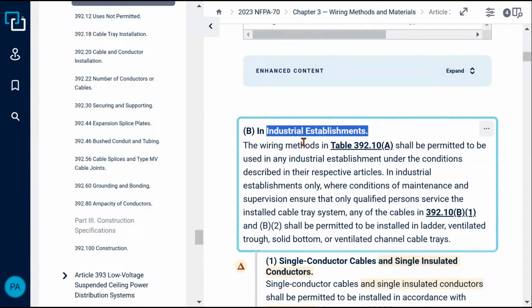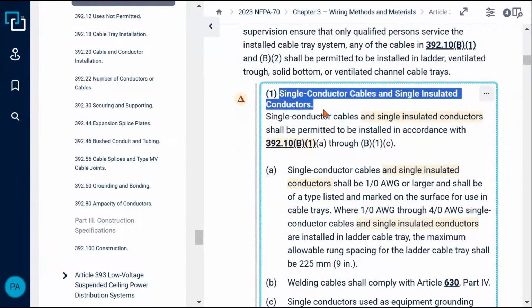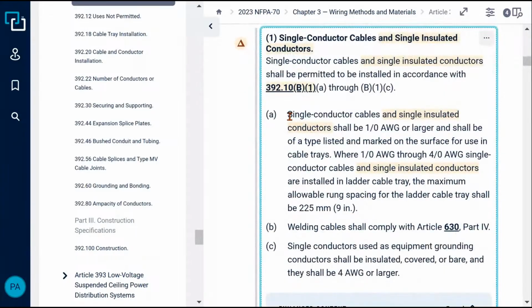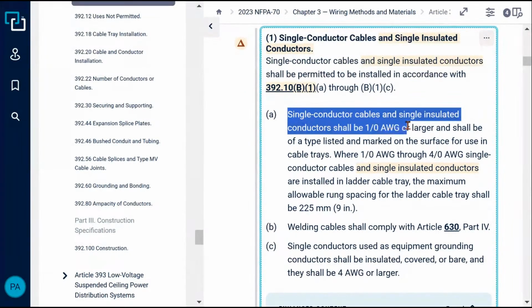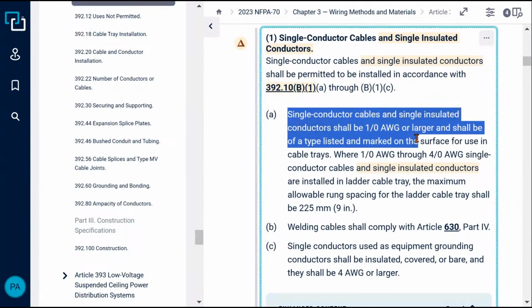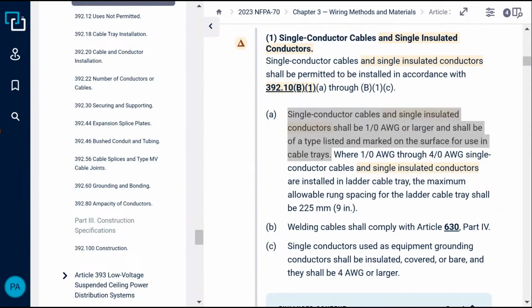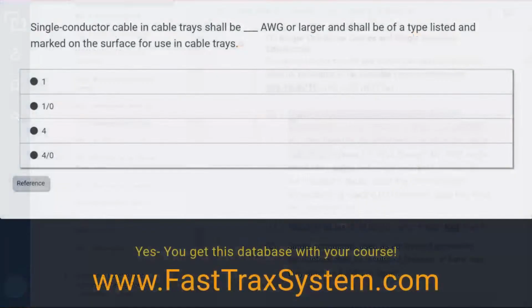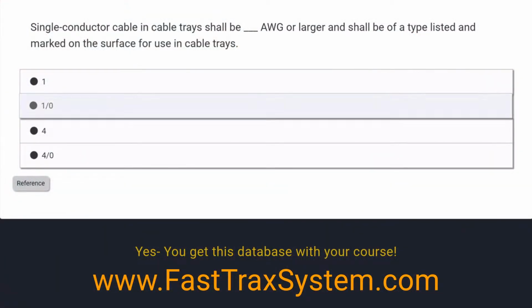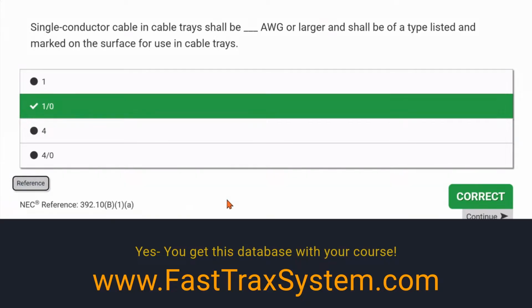And when you do, then it gives you this rule: single conductor cables and single insulated conductors shall be 1/0 and larger, and shall be of a type listed and marked for the use in cable tray. So 1/0 and larger is the answer there, and there's our reference right there. Makes sense? All right, let's do another question.